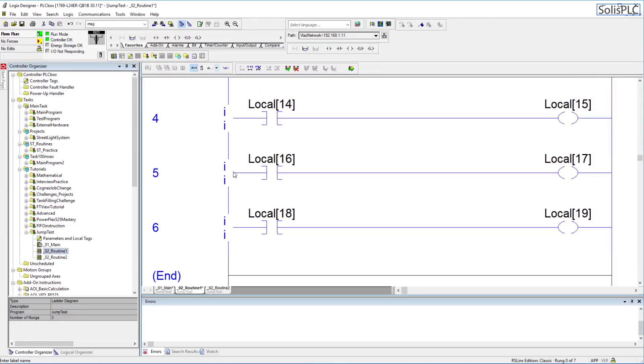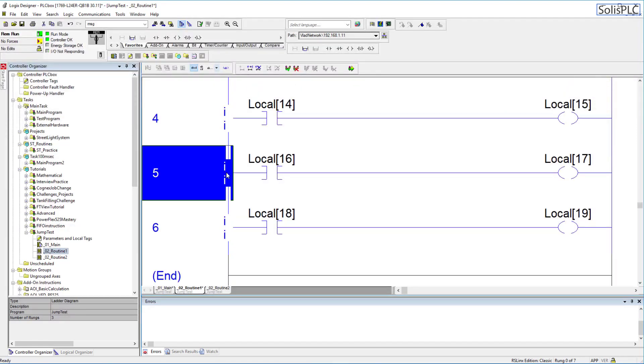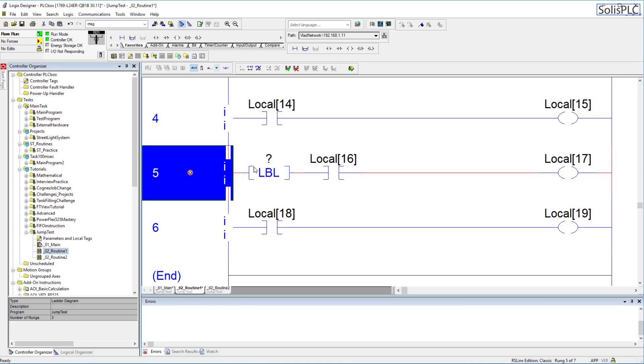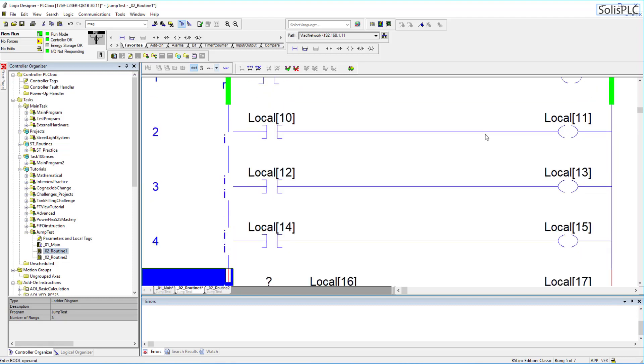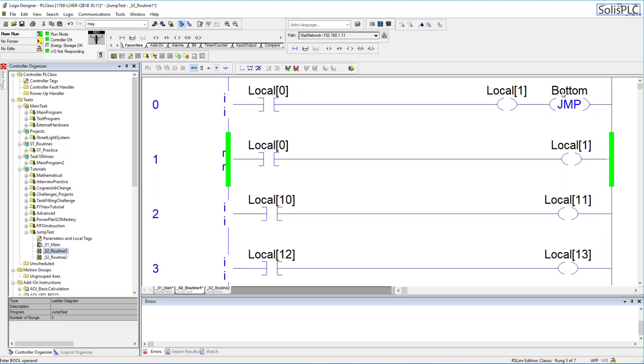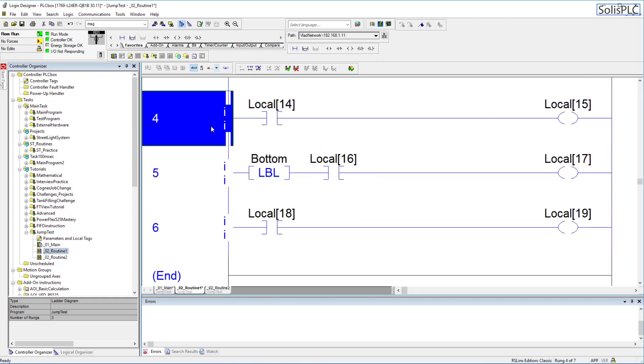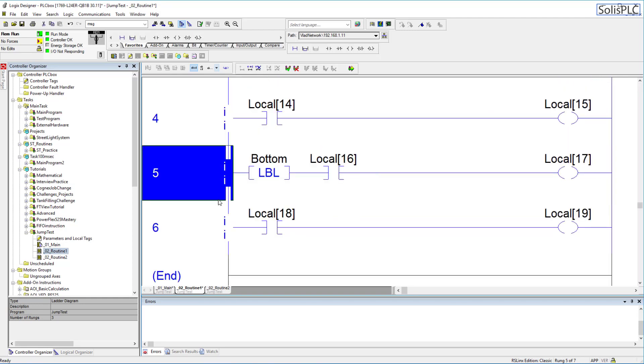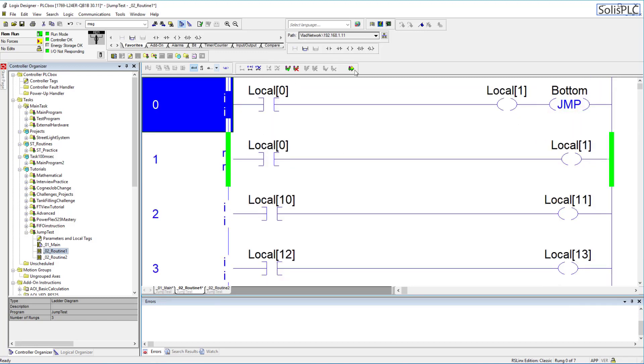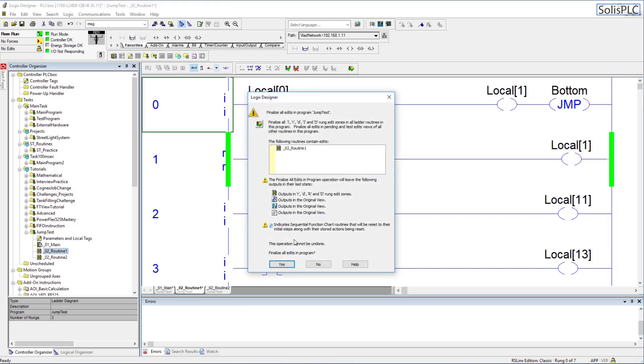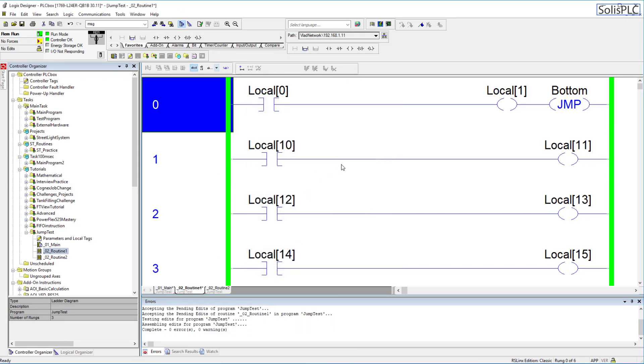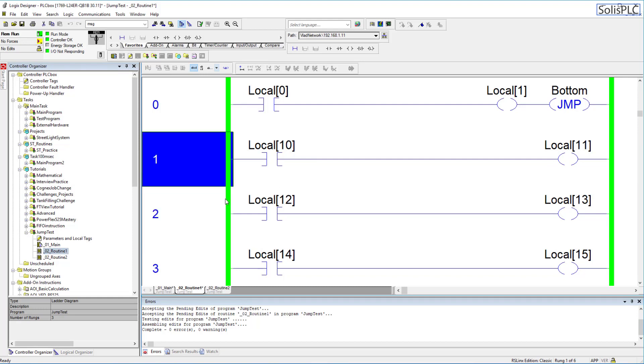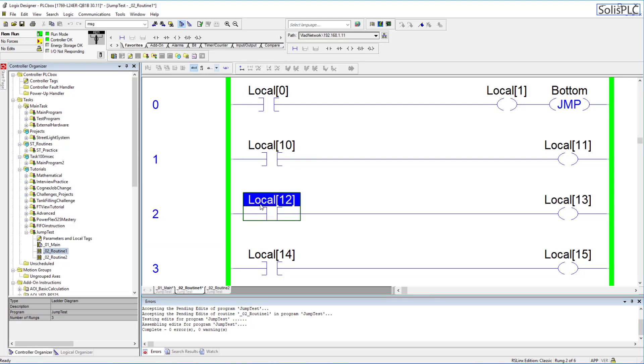Now what is required is the label to be placed on something else in order for this instruction to know where to jump so what I'm going to illustrate here is I'm going to jump to this specific rung and I'm going to label this as LBL so LBL are the other three letters that you want for that instruction and I'm going to copy this label so essentially the labels need to match on both instructions so here's our bottom label here's the jump and I'm going to complete or essentially compile all of that simple logic so there's nothing nothing too intricate but we do have this jump.